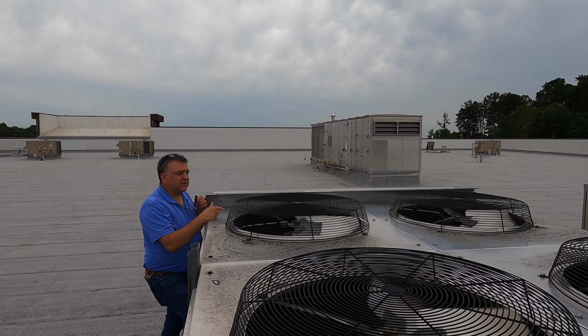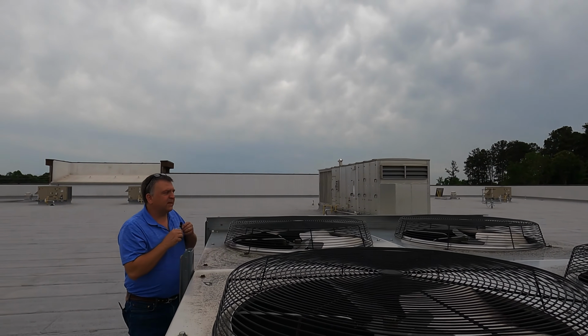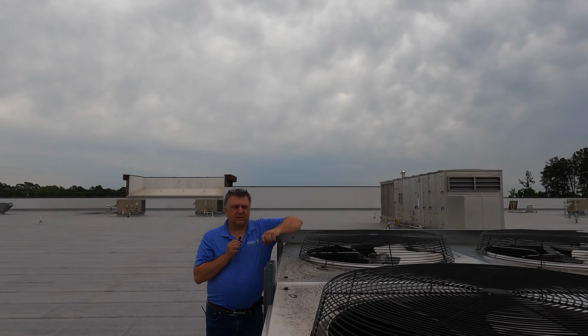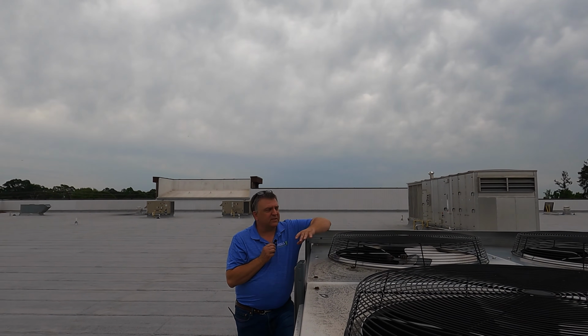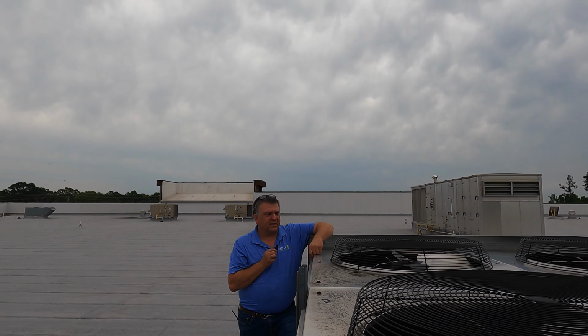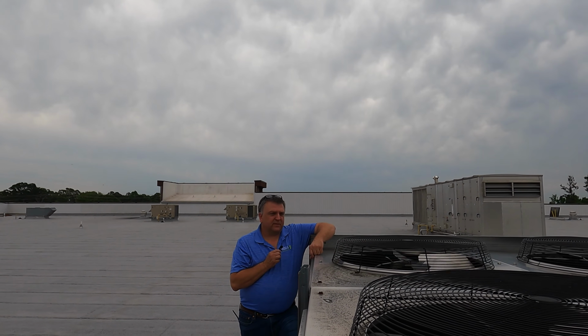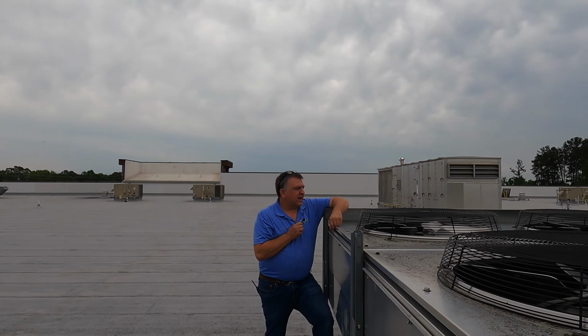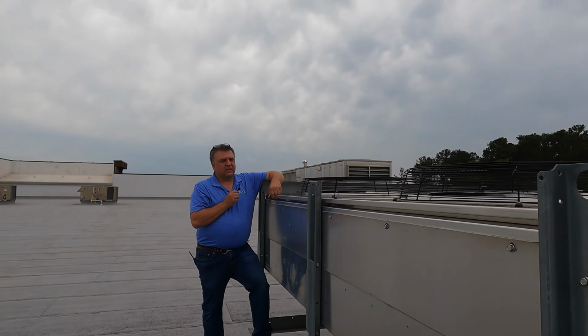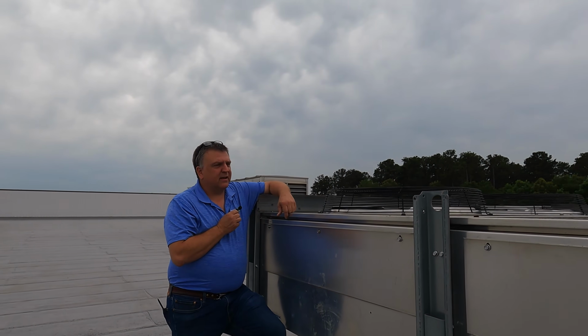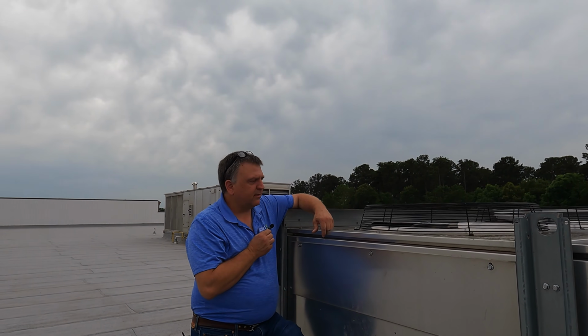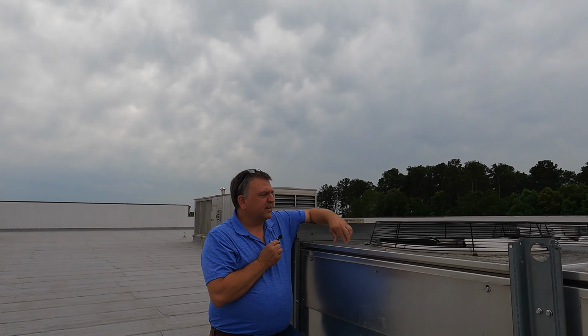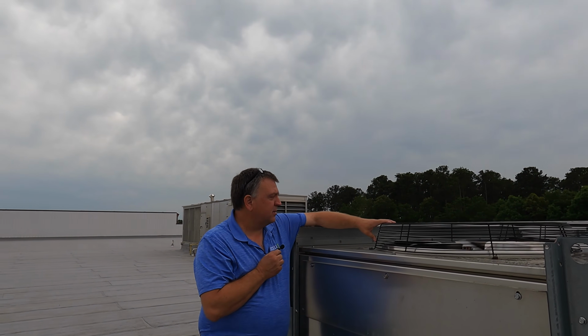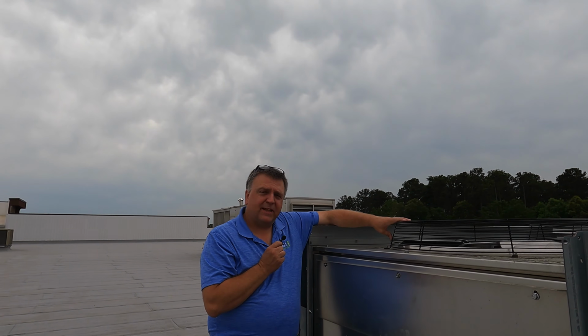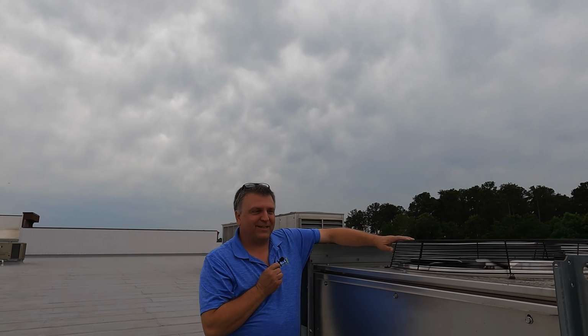Now they do have the technology now, and I think these have it. I'm not sure if I've set them up that way, where you can go 0 to 10 volts, with 0 volts being 100% and 10 volts being 5%. And they do that for a fail-safe reason. So if I lose a board in this rack in the middle of the night, these condensers will go to 100%, and I'll end up just having a really low head pressure that I'll have to fix. But I'm not tripping out on high head, which helps the compressors, helps with short cycling. They're efficient motors, they're good motors. Like I said earlier, everything made by man is subject to fail, so they do need replacing every now and then.